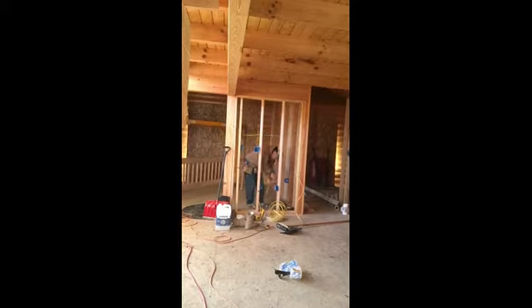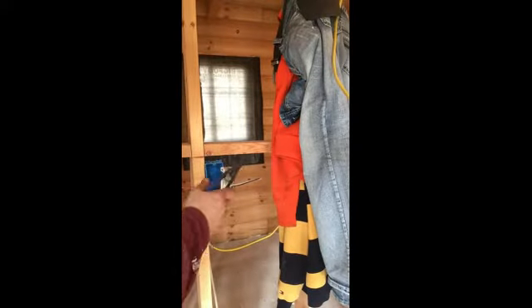This is so that you can go back through and install the plug and switches later. So that's something that we'll do later. Remember that it's the first plug and it's going to power the entire room. So you need to wire all the plugs in the room from this one plug. So you're going to run pigtail wires from that one plug to all the plugs, and then you're going to have to pigtail it to the switch for your lights in the room. Usually there's one light in the room, so let's just go with that theory for now. You got one light to wire, so you're going to wire from that one plug that's been powered.